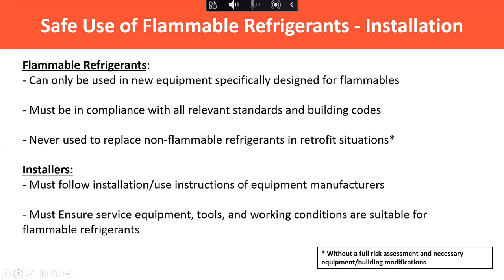Flammable refrigerants are only going to be in new equipment. They're going to follow standards and codes and they're not going to be used in retrofit. The installation of this equipment is going to be a little different, so if you're an installer, it's important that you read and understand all the installation instructions from the equipment manufacturer. Certain things will be different, a lot of things will be the same, but make sure the installation goes according to plan. Further down the line, when the equipment needs to be serviced, make sure all the work practices and tools are correct, and I'll get into details on what that means.